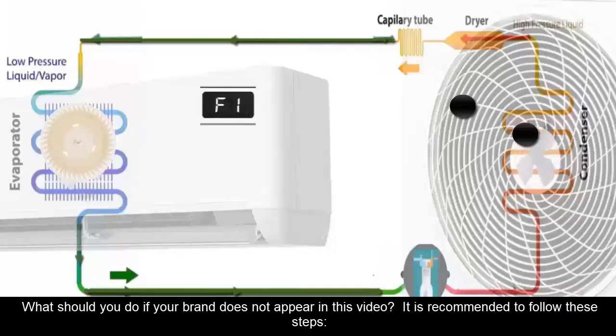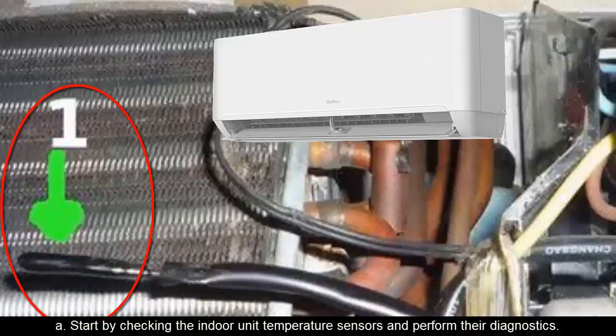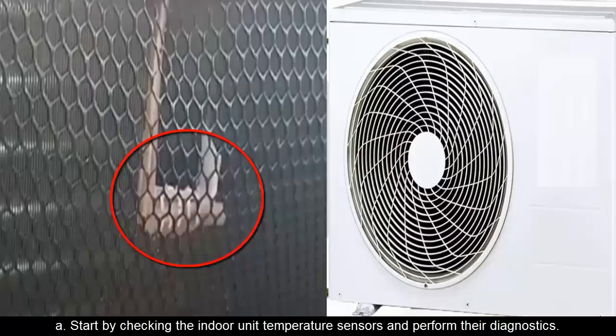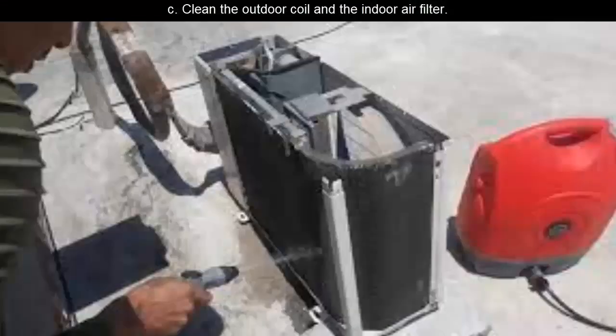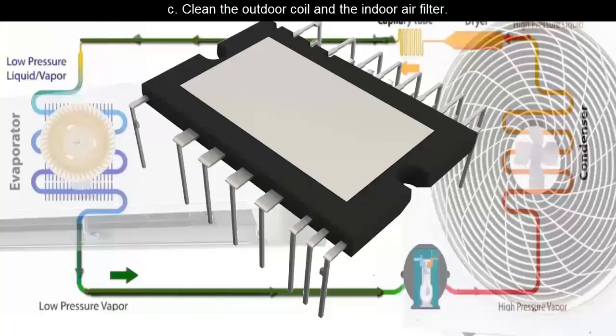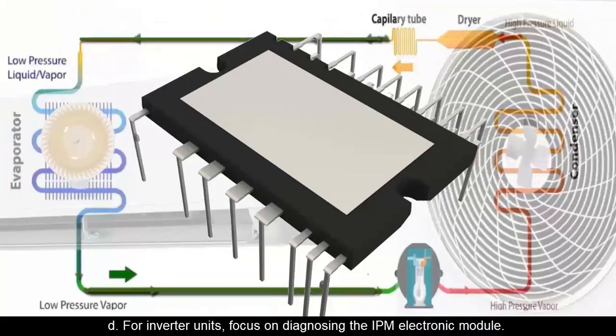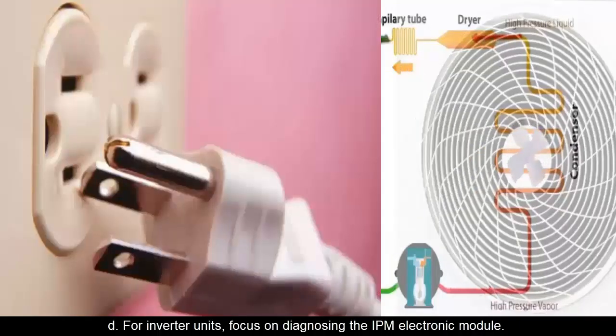What should you do if your brand does not appear in this video? It is recommended to follow these steps. A. Start by checking the indoor unit temperature sensors and perform their diagnostics. B. Then verify the outdoor unit temperature sensors if your system has them. C. Clean the outdoor coil and the indoor air filter. D. For inverter units, focus on diagnosing the IPM electronic module.